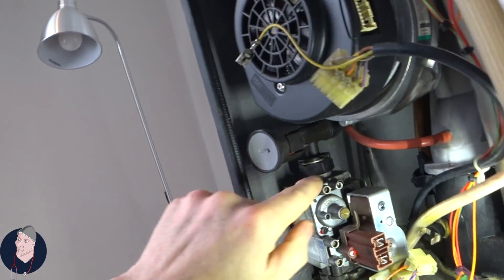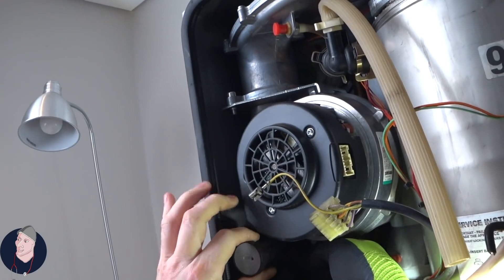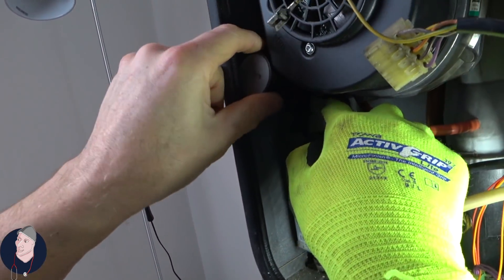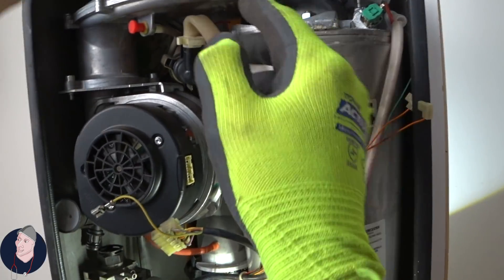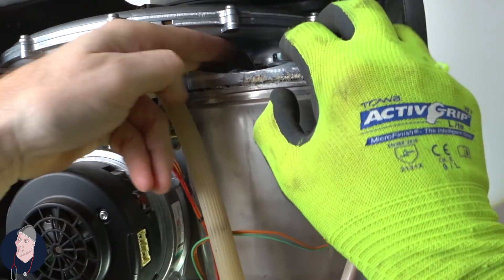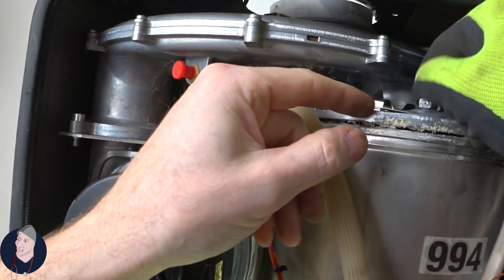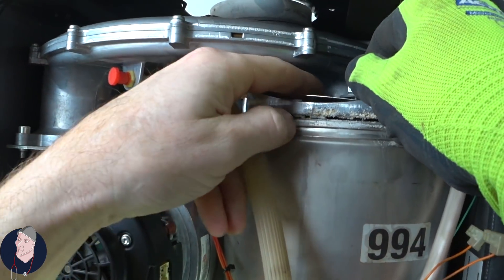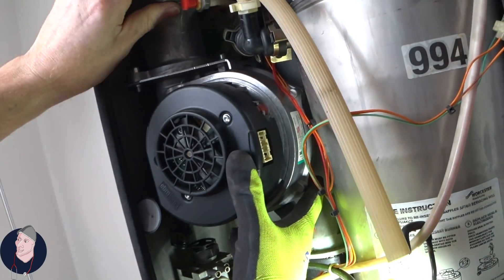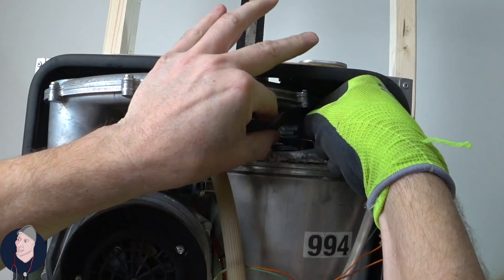There's a pin here — you basically pull that out, pull this up, now lift this up, so you're out. Quite often that will give you grief. I'm going to whip this out — ratchet spanner is your friend here. Crank that. A little spring there, lift that tab over, a little bit of a wiggle, that's you. Typically I'll just take this completely out — you don't have to. If I remember right, you don't even have to take the electrodes or any of the cables off, simply spin.